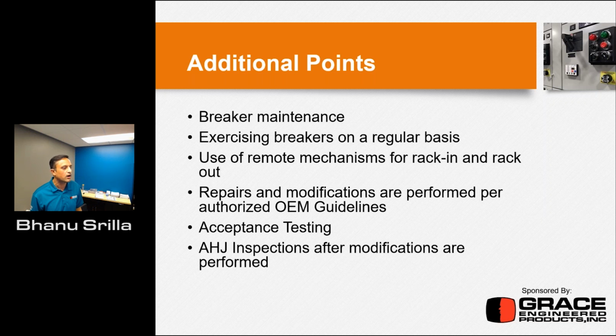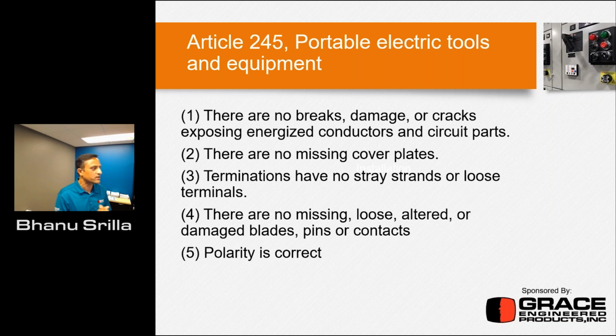And repairs and modifications are performed using authorized OEM guidelines. So this one is really important, because whenever you do any kind of service work on your MCCB or your breaker, you need to make sure that these things follow the manufacturer guidelines. And if you make any kind of modifications to the gear, a good example would be you just put in IR windows, for instance, right? You need to make sure that the IR windows align with the manufacturer guidelines, and the OEM has approved those things, right? And acceptance testing, because if you make any kind of physical change to the system, you probably need to have an AHJ inspection after the modifications are made to make sure that the system is restored to its normal original working order.